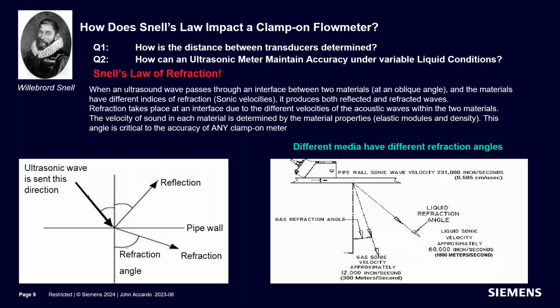Now, the other thing you might see on the right side is the gas sonic velocity and the refraction angle for gas. It's much, much steeper, much closer to the normal, because the speed of sound of gas is so much slower than that of liquid. It's about a fourth of what water is at a given temperature. So again, that changes the position of the transducers. When you program the meter, you tell it what your fluid is, and from that information the meter has a rough idea of what the speed of sound should be. It uses that information to calculate what the transducer spacing will be so that it intercepts the refracted sonic beam.